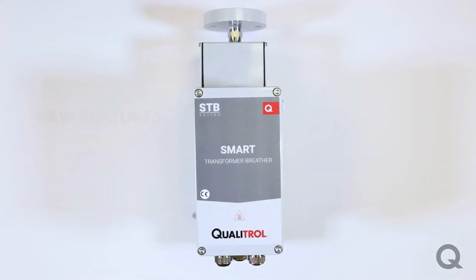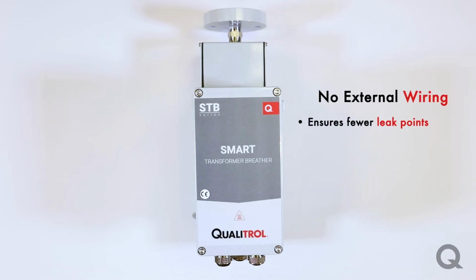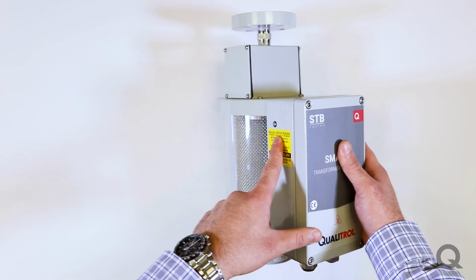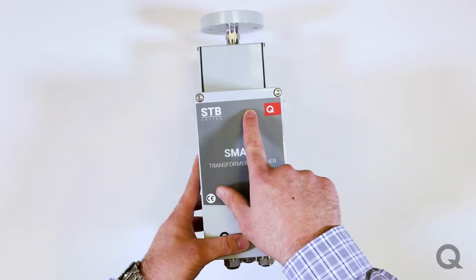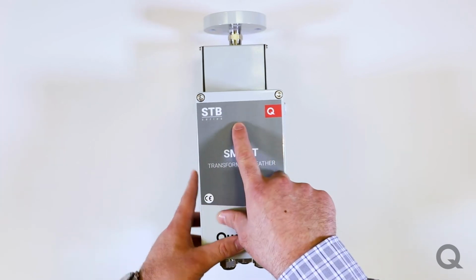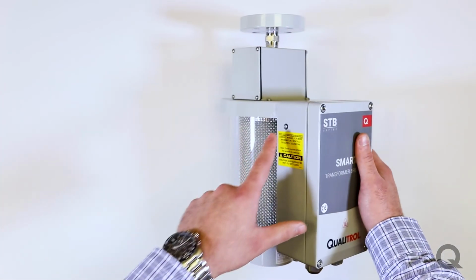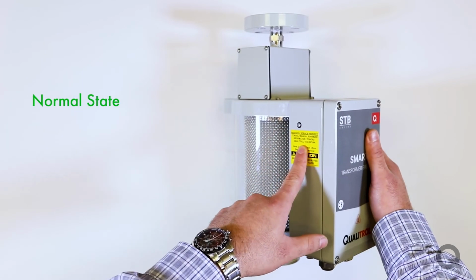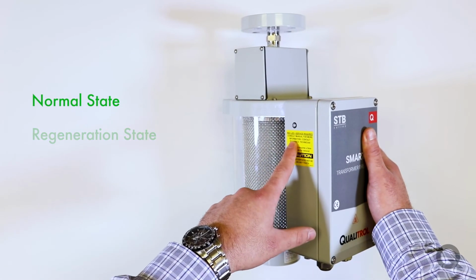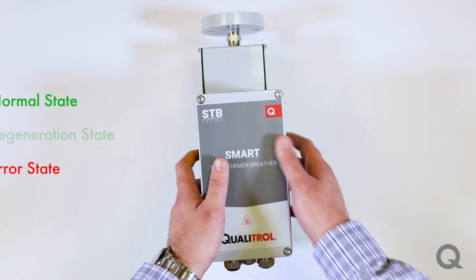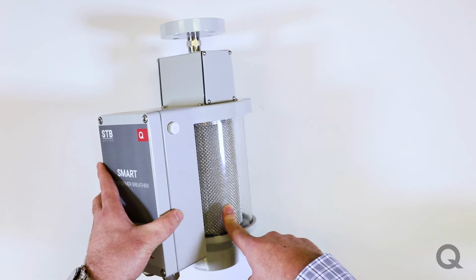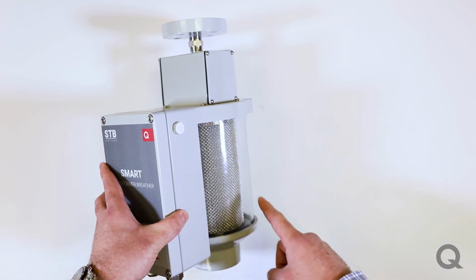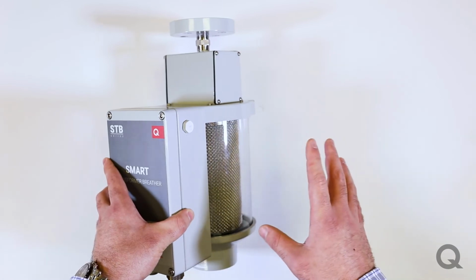So moving closer to our new transformer breather, a new feature that you can see is that we no longer have any external wiring. Internal wiring ensures fewer leak points through loose connections on the external cabling, and also eliminates the risk of any unintentional damage to those external wires. Another new feature we have is that we moved to a single side LED. Previously we had 3 front-facing LEDs with 3 different colors for different breather statuses, and now we have one single side LED that is either solid green in a normal state, blinking green in a regeneration state, or solid red in an error state. And the third physical feature is that we're moving to a glass tube as a standard. Previously we were polycarbonate standard, now we have the option of either glass or polycarbonate, with glass being the standard.